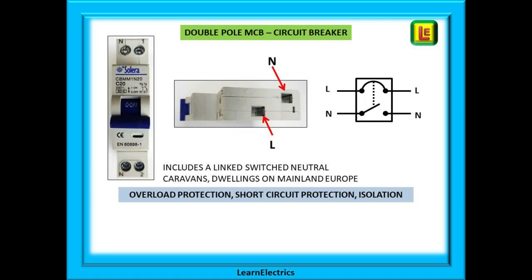A third construction of an MCB is the two pole device. These are obligatory on mainland Europe and also used in caravans in the UK. The neutral must be disconnected at the same time as the phase, so there are connections for phase and neutral on each MCB. The standard number is still EN 60898 but without the BS prefix. Otherwise they have the same protection and switching characteristics as the UK versions.